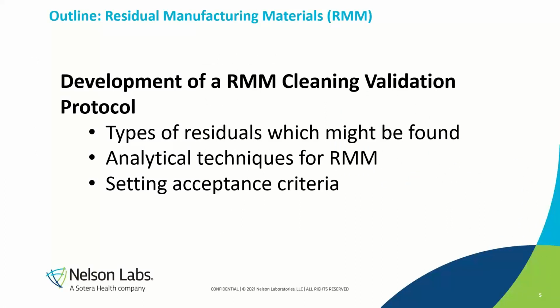So now let's get into the development of a cleaning validation protocol. One of the first steps in the risk assessment of a device is to identify potential residues which may be found on the device. So, you know, what type of chemicals are used? Are they directly or indirectly? What type of debris could be produced? That type of thing. Once this list of potential contaminants is available, we can then categorize the contact agents and select an appropriate test method and acceptance criteria. So we're going to break this down in a step-by-step format.